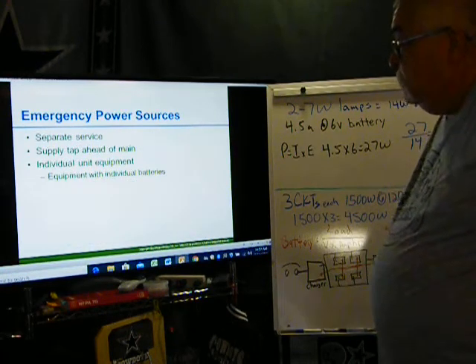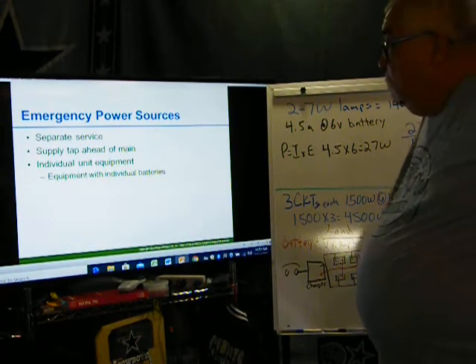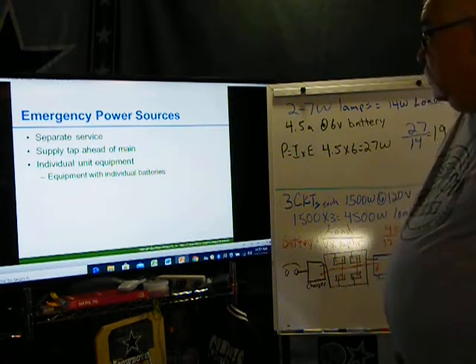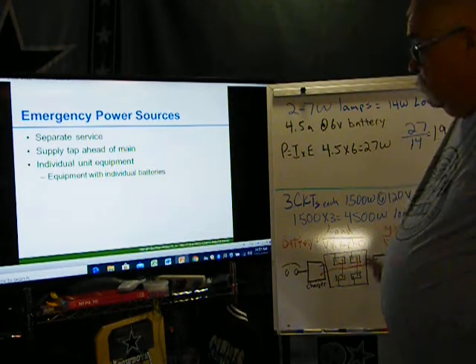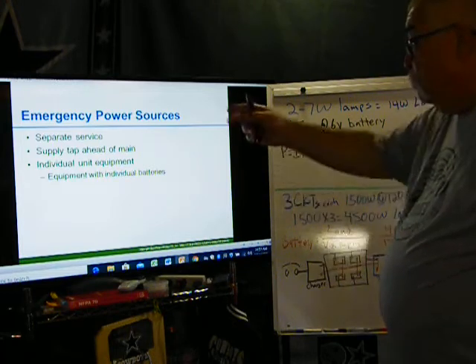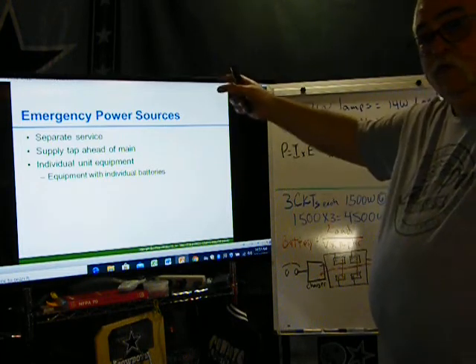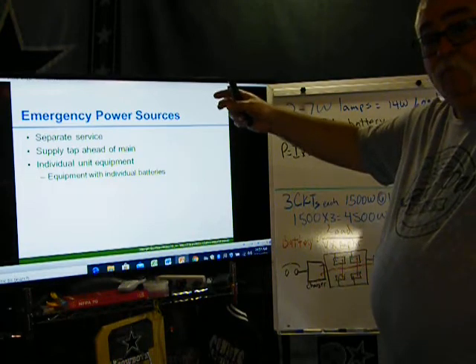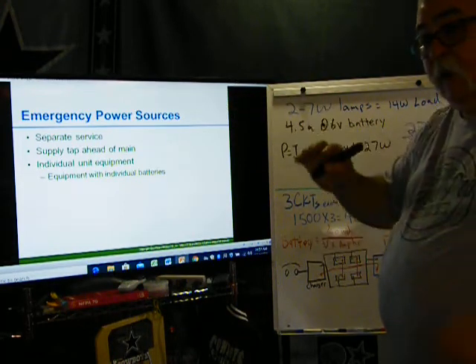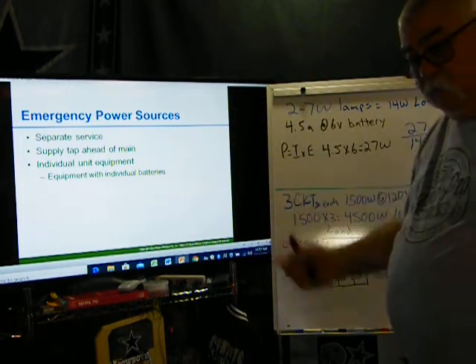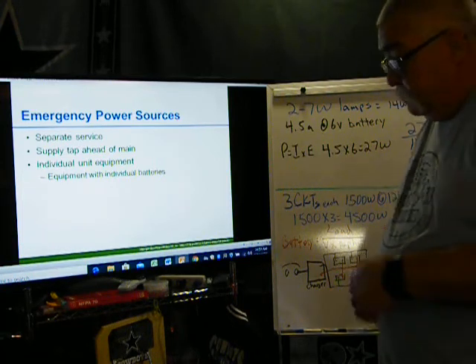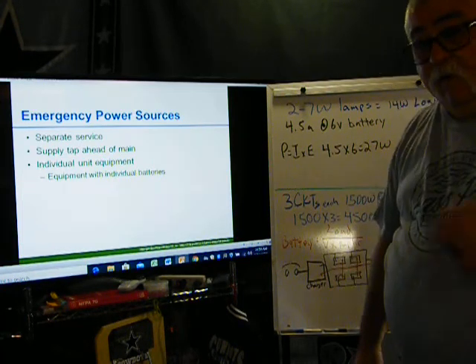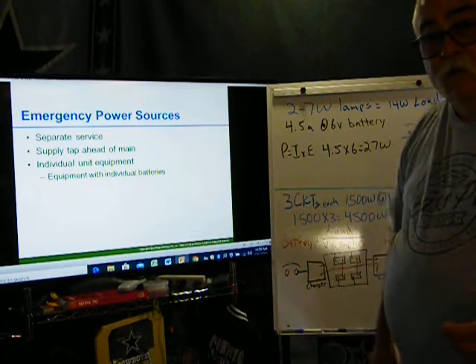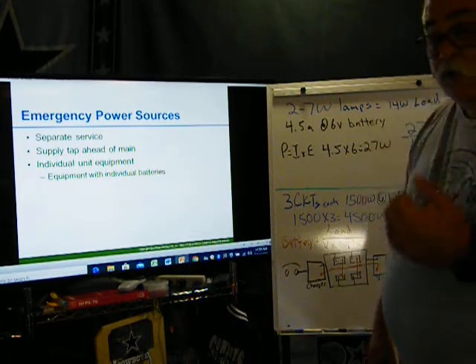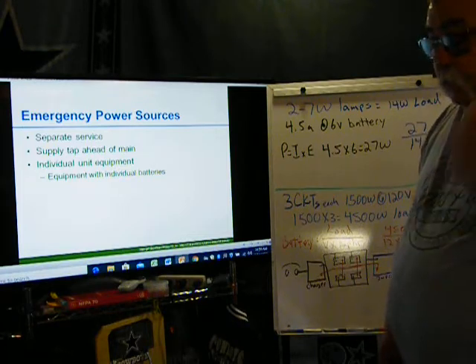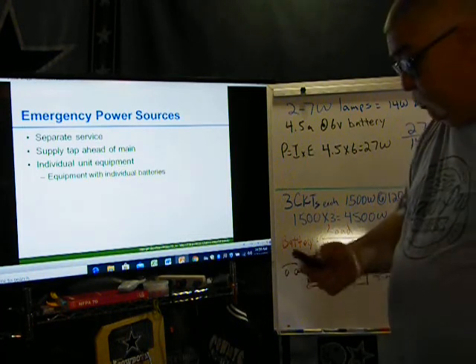Emergency power source: you can have a separate source, a supply tap ahead of the main, or individual unit equipment. So equipment and batteries, we're talking about the equipment and the batteries, and we talk about a separate service. Guess what? You bring two services into your building. You run off of one, and then you have a bypass, in case one goes out, it transfers over to the other. Okay, that's only if you have a problem, let's say the main breaker goes bad. So now it transfers over to the other one till you change the main breaker. That's good. But if utility goes down, well, guess what? You're out of power too.